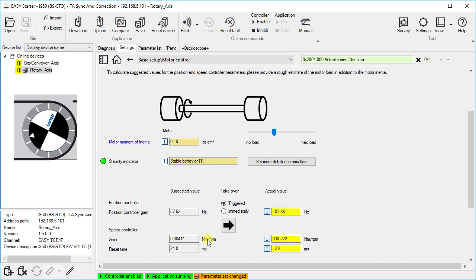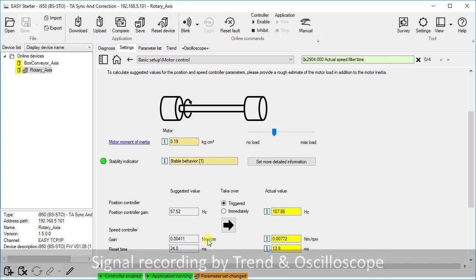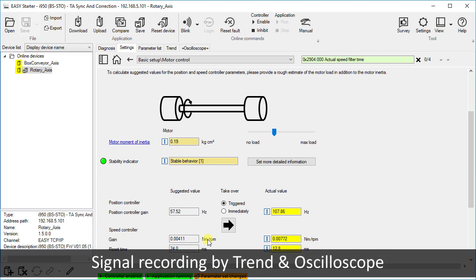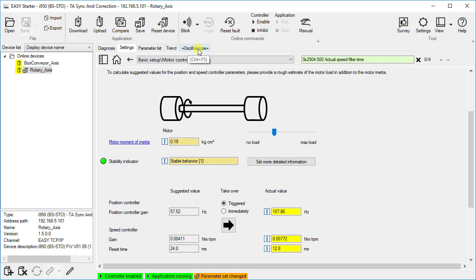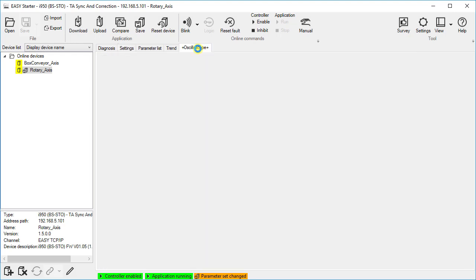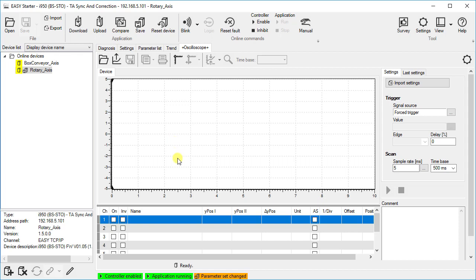Next, we will look at the changed drive characteristics using the oscilloscope. Let us record relevant motor control signals and evaluate the drive behavior during a drive stop. In comparison to the trend function, which is better suited for logging continuous processes, the oscilloscope is designed for recording highly dynamic processes. Configuring and starting the recording is only possible when an online connection to the inverter has been established. After the measurement is completed, the measured data is transmitted and represented graphically on this oscilloscope user interface. The oscilloscope has eight channels.